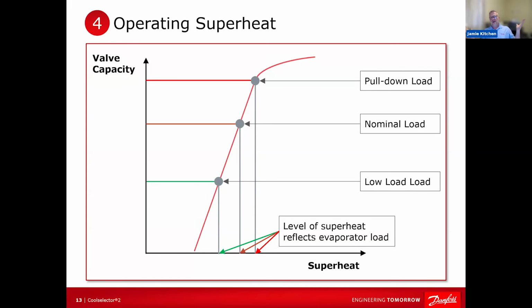And you may think, oh man, if low superheat's so efficient, why don't we just dial this superheat down? Well, you can, but here's the problem. Every evaporator has what's called a minimum stable superheat curve. And see how that TXV's got a straight line? That minimum stable superheat is curved. And so if you go too far, it's going to be inside that curve at one point, and you're going to start getting liquid shooting out. You might be measuring 3 or 4 degrees of superheat, but you've got liquid going down the center of that pipe, and that's going to start the valve hunting. And so it becomes unstable.